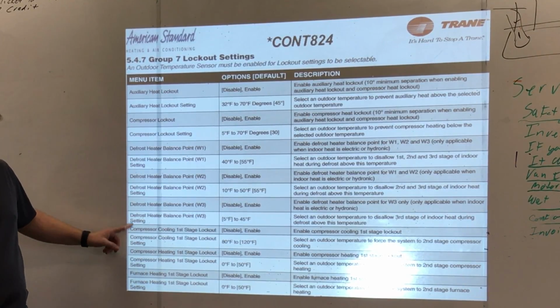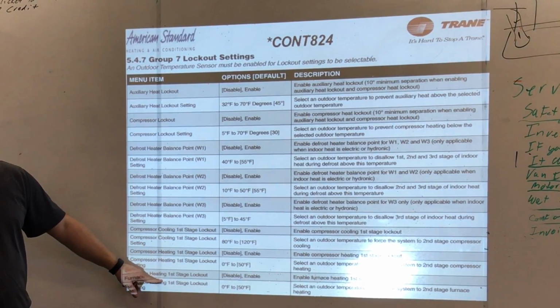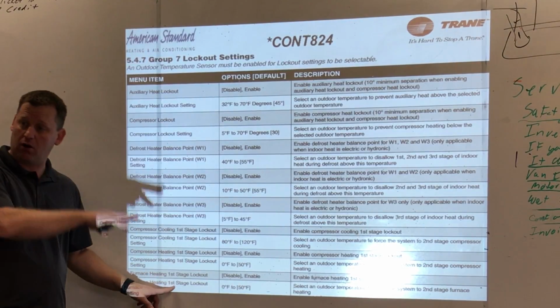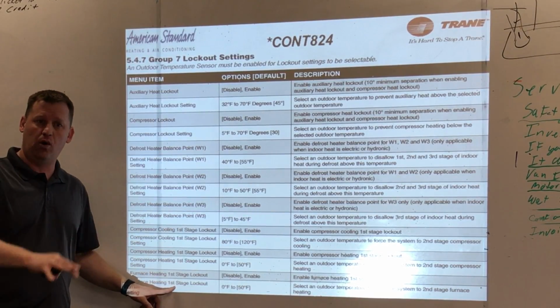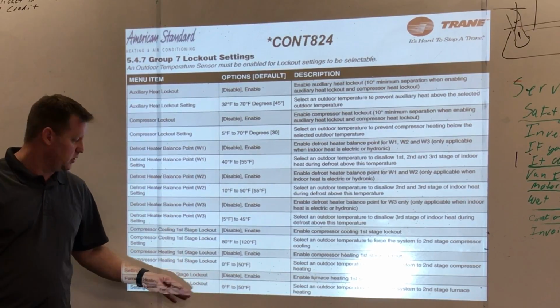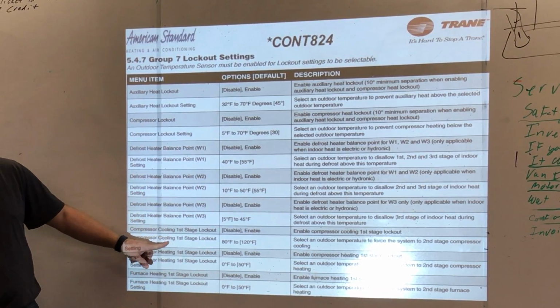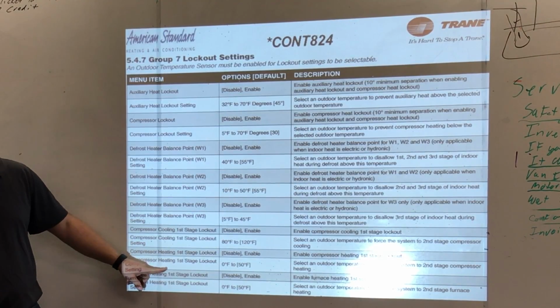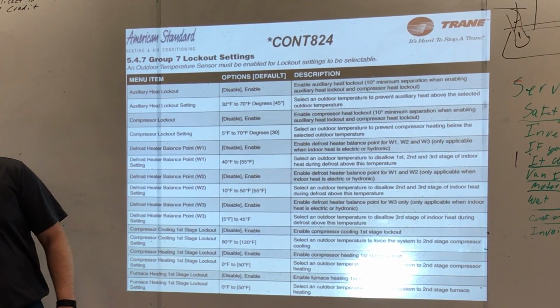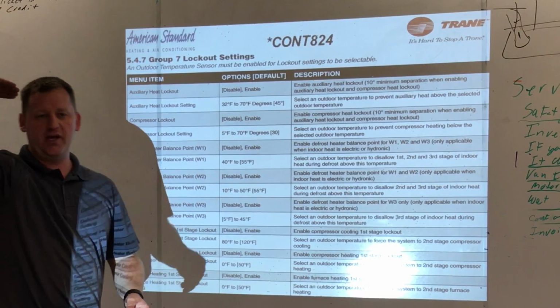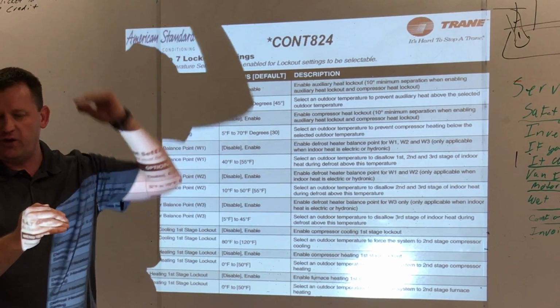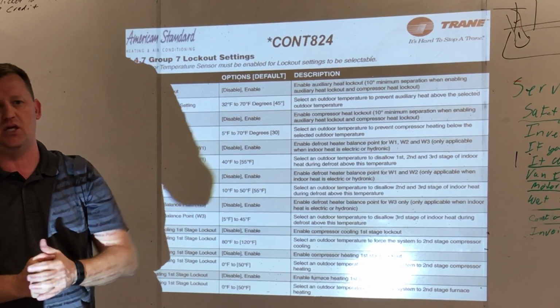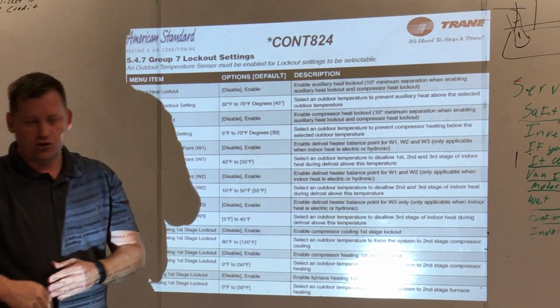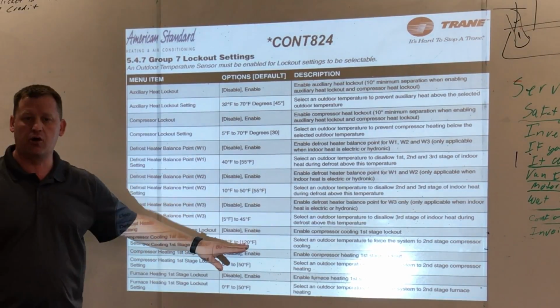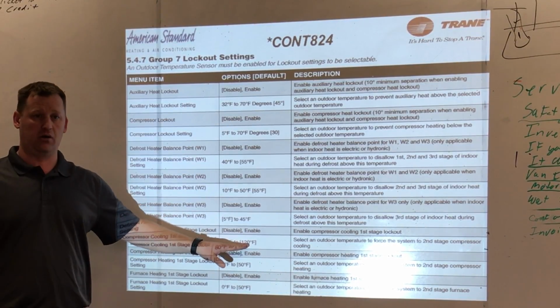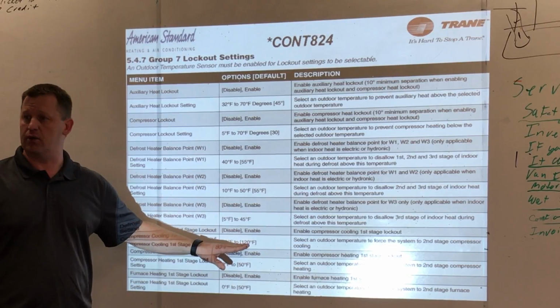So this is first stage lockouts based on outdoor temp. Again, you have to have a hardwire outdoor sensor. Internet weather will not give you these capabilities. So there's compressor cooling first stage lockout, compressor heating first stage lockout, and furnace heating first stage lockout. You can tell it, when we get to this outdoor temp, don't even run first stage cooling, just go right to second stage because we know we need it. Like you could set first stage cooling lockout at 100 degrees, because we know at 100 degrees we're going to have to be cranking this unit.